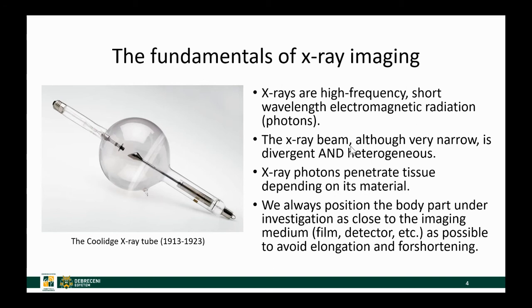A little about the fundamentals of x-ray imaging: x-rays or photons are high-frequency, short-wavelength electromagnetic radiation. They are generated in x-ray tubes, which haven't changed much since they were invented. Even though the beam that exits this vacuum glass is narrow, it's quite divergent — that's why we need shielding.